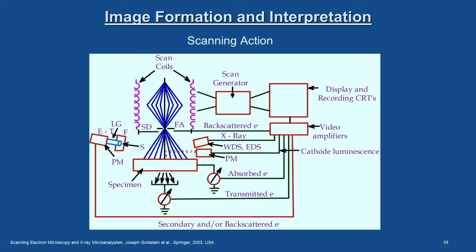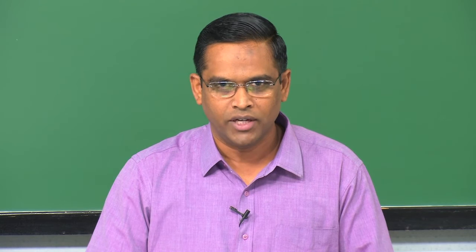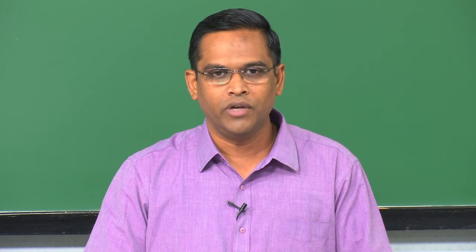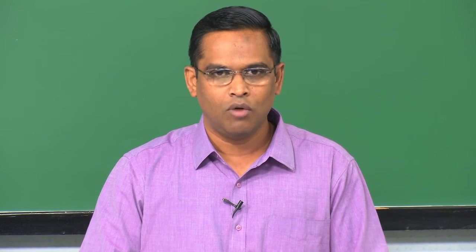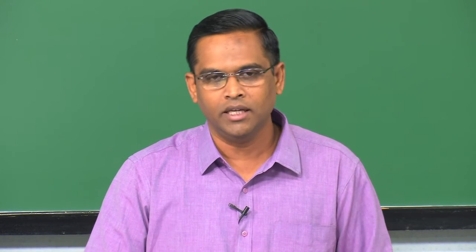When we say the electron beam is falling on a specimen and gives out a signal, we always talk with respect to a particular point — the signal coming from the specimen surface, whether it is a characteristic X-ray, a secondary electron, or a backscattered electron, allows us to interpret the specimen surface at that particular point. If we are interested in the complete surface area, the beam has to scan from one point to another, point by point.